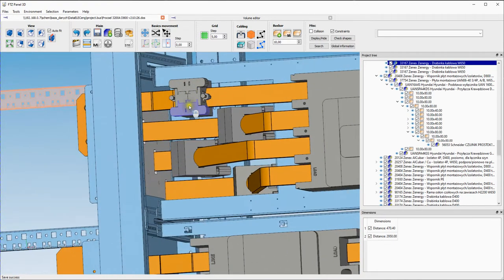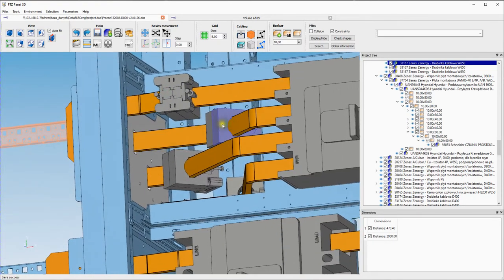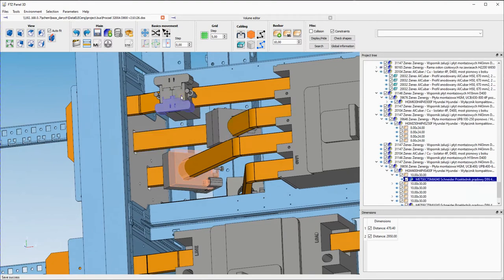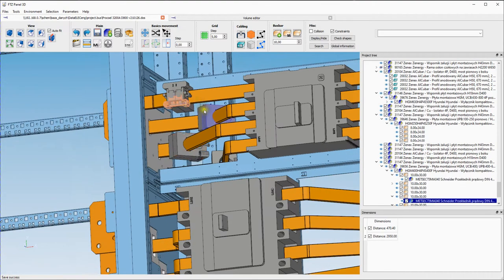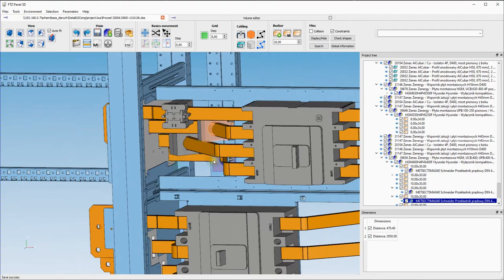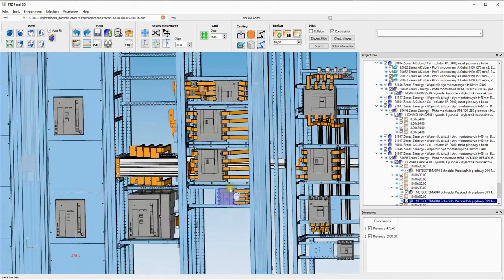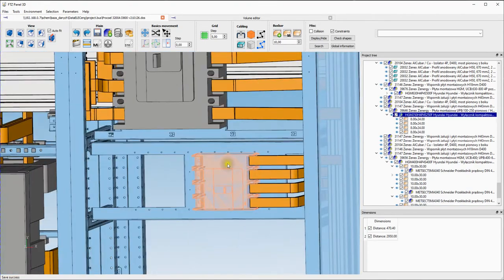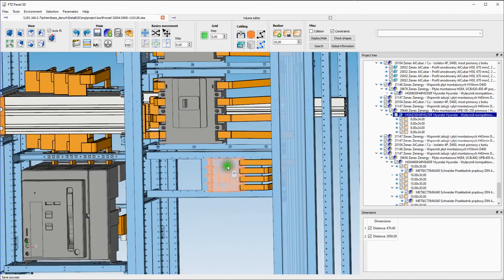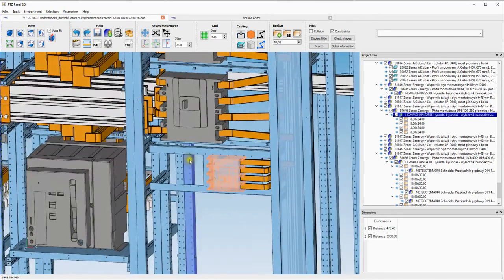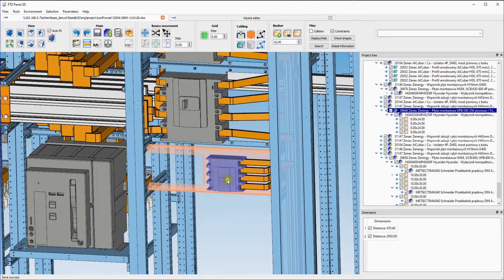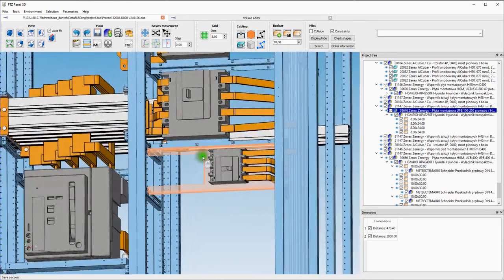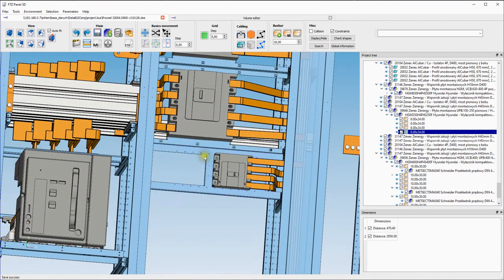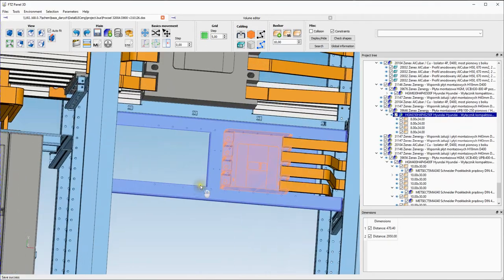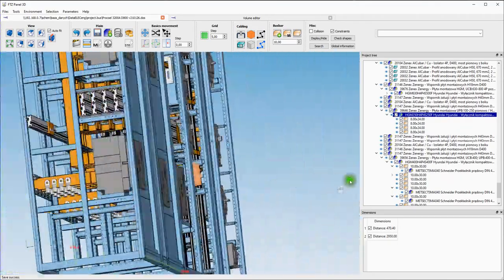So here should be the toroid. Here I only drew that if you would like to have some measurement with some analyzer, you can add current transformers. Below there is this small breaker which is 250. The same situation, the toroid is quite big, you will not put it here. Here you can put current transformers. I didn't draw the outgoing bus bars from this breaker, it has no sense.